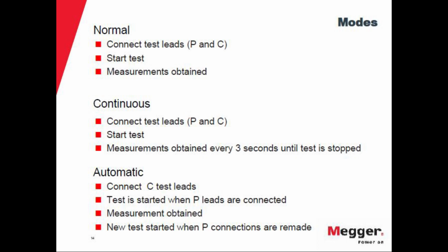The continuous mode is more for testing a switch gear, for example. You connect the current from one end of the switch gear to the other, and then you go and measure different points. You connect the leads, and every 3 seconds it will obtain a result. So you can go and test and make some adjustments to the sample if you want. And the automatic mode: the current leads are always connected, and the measurement starts when you connect the potential leads. Every time you connect the potential leads at different points, you get a different resistance value. So the instruments will have different modes, and depending on what application or what you are testing, you can obtain your results faster or easier.